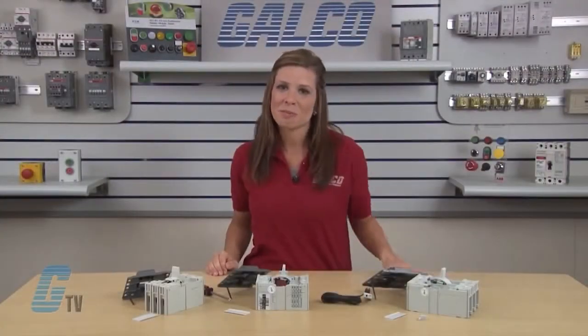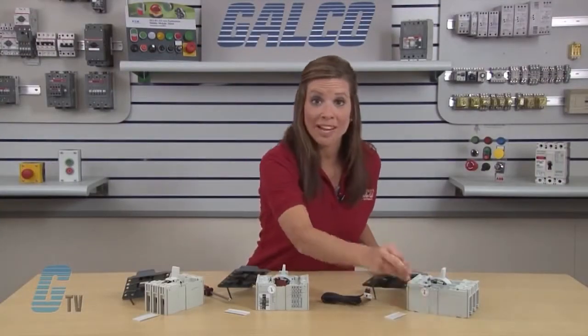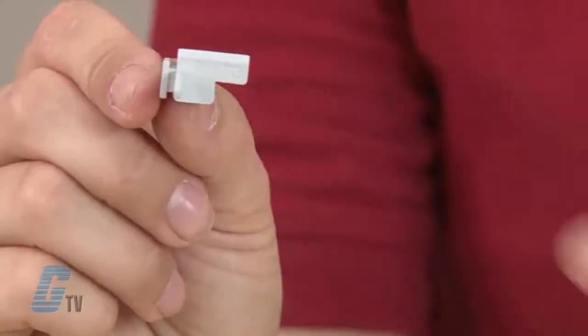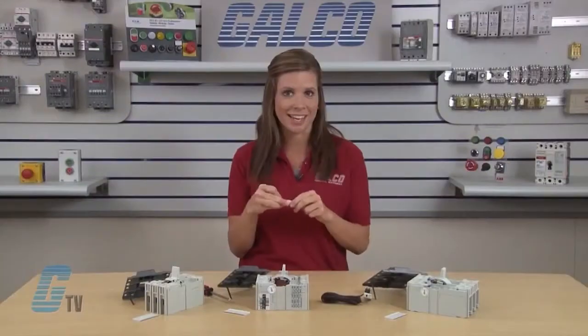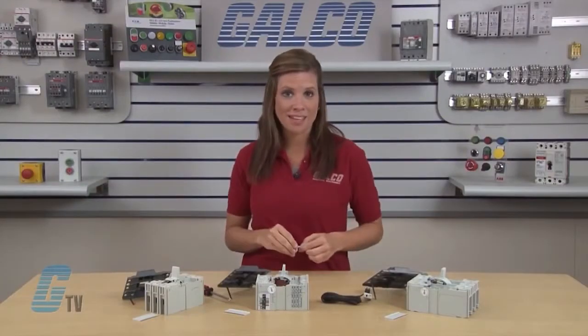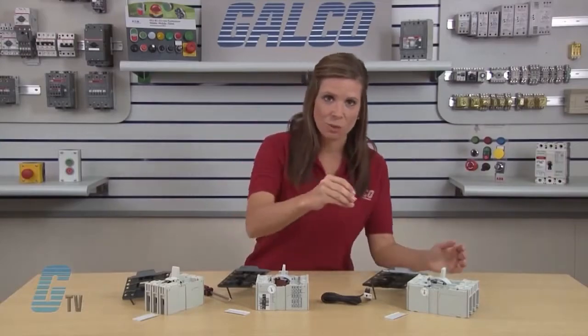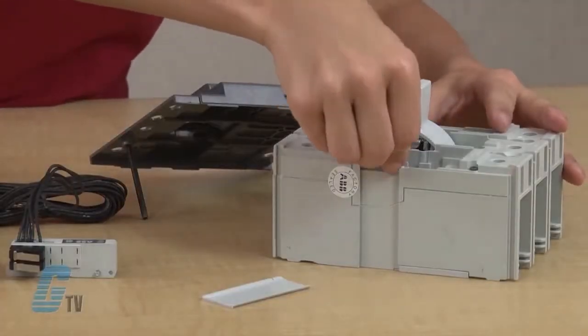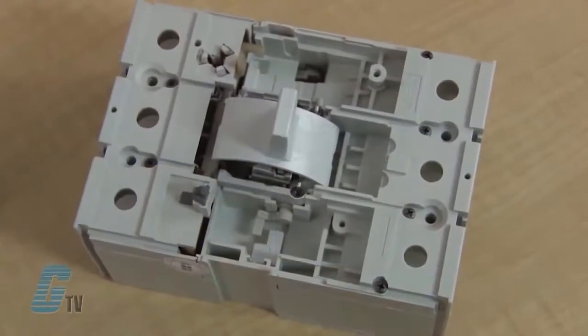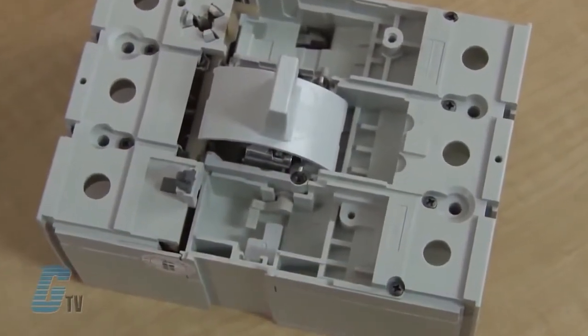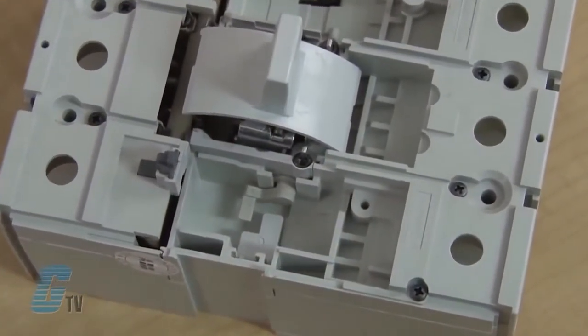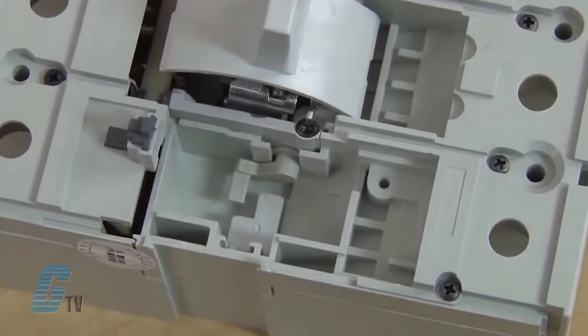For the T3 circuit breaker, I'll select the off-white adapter, which is also marked with T3 molded in the plastic. I will insert the tapered tab into the slot at the back of the accessory port, while the tab on the right slides into the grooves on the right side of the circuit breaker frame. The adapter is seated properly when it drops all the way down freely into the slot.